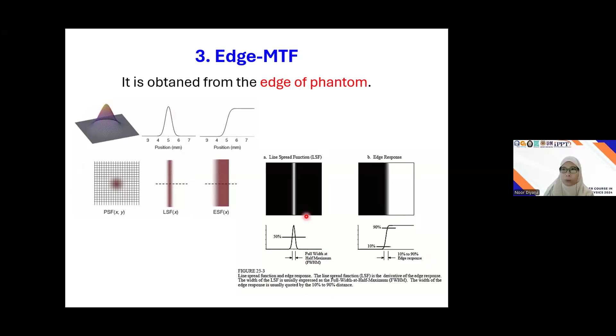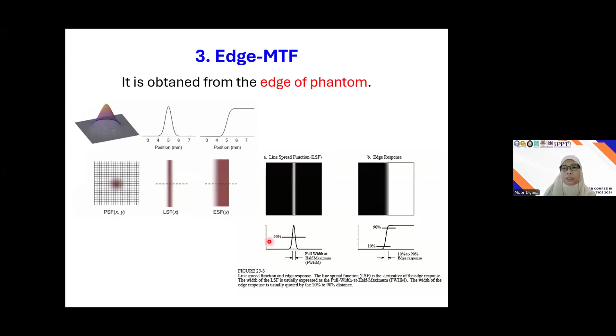And then for edge MTF, usually it is obtained, oh sorry, typo error here. It is actually obtained from the edge of the phantom. Sorry, my mistake. So usually we measure edge MTF from the edge of the phantom. Edge response is actually to see the separation between the edge of the object and the background. And then the line spread function actually depends on the line. This is the line spread function and this is the edge. So the graph will be like this, and this is the graph for LSF. The line spread function is actually the derivative of the edge response. LSF is usually expressed as full width at half maximum, FWHM.